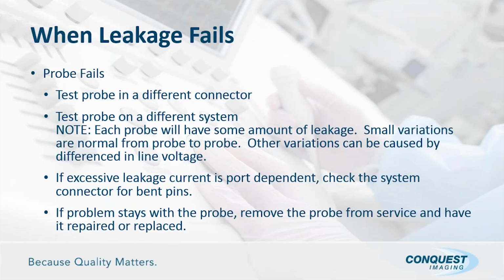So at that point, I'll put a comment on the report: although the M12L probe meets electrical safety requirements, the leakage current is unusually high and it should be removed from service and repaired. I want my customer to know that yes, it passes. I'm not trying to say that it doesn't pass, but I've tested 10,000 probes and we don't commonly see it this high, so there's something wrong. So I think it's okay to notify your customer when you see this condition even though it passes.